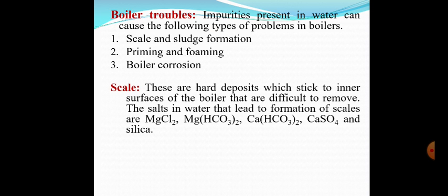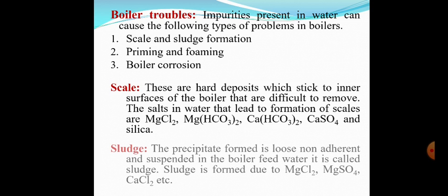Scale is nothing but a hard deposit which sticks to the inner surfaces of the boiler and is difficult to remove. The salts in water that lead to the formation of scales are magnesium chloride, magnesium bicarbonate, calcium bicarbonate, calcium sulfate, and silica. Scale may be formed due to many inner reactions which also occur inside the boiler.